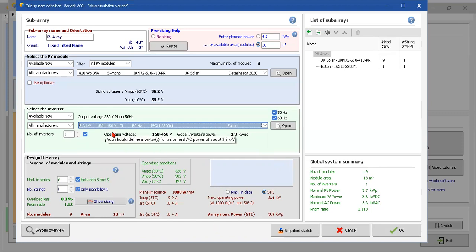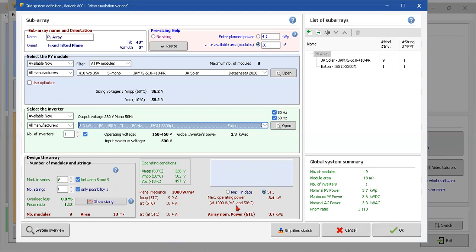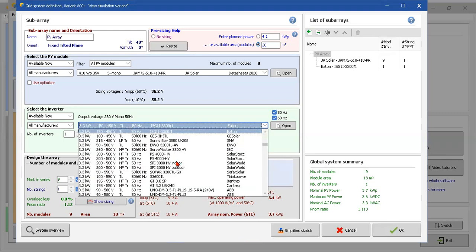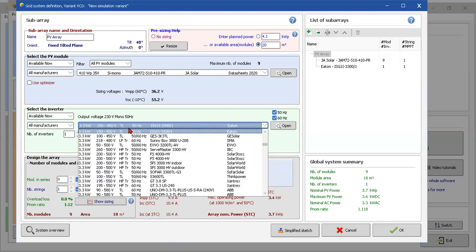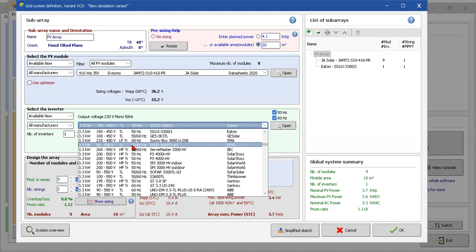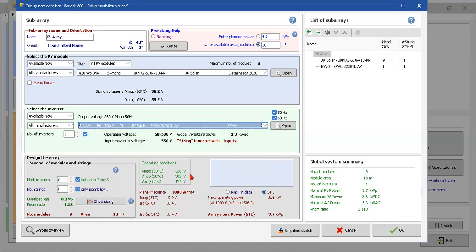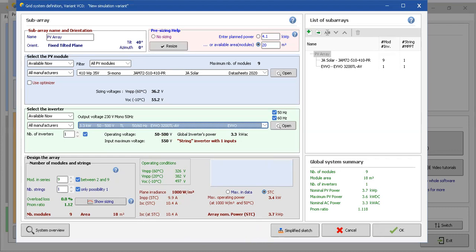The array is greater than the inverter for maximum input voltage. Okay. So the voltage behind it - this one. Yes, we have the operation condition of the array here. Okay, okay. This is the operation voltage of the inverter. And these are the operation conditions, which is the voltage of the arrays. So all this number must be here, or at least closely. And these two - Vmpp in 60 degrees, Vmpp in 20 degrees. If I choose this one, this is going to be better because all these voltages are here in this operation voltage.